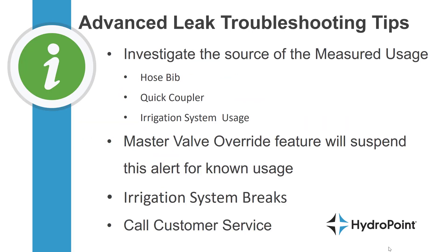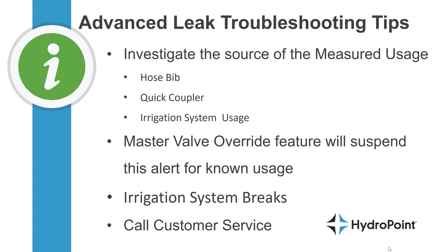When troubleshooting an advanced leak alert, start by eliminating the easy stuff. Talk to your maintenance folks about any use of hose bibs, quick couplers, or manual manipulation of the irrigation system that might have caused this alert. Remind anyone managing the system this way to use the master valve override feature available from the manual menu at the controller or on WeatherTrack mobile, which when active would prevent the controller from creating an advanced leak alert.